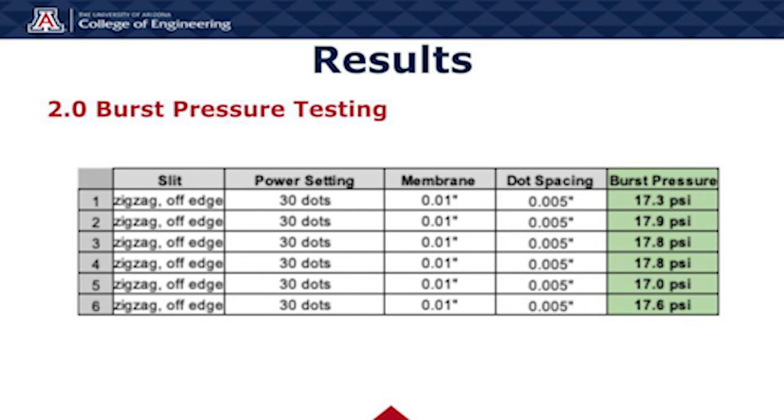The average burst pressure was 17.5 psi. While the burst pressure is not as low as the original specifications of 9.1 psi, we have shown proof of concept and our data indicates that this method of lowering the burst pressure using intentional slit geometries is possible with access to more advanced laser cutting technology. For reference, we determined that a membrane of equivalent thickness without an intentional slit geometry will burst at 24 psi. The laser cutter we used caused minute differences in the thickness of the slits resulting in weaker points throughout the cut that would cause small leaks. As a result, the pressure had to be increased past the design specifications to cause a full burst after these initial small leaks. However, while we decided with our sponsors at Ceridian that 9.1 psi would be an ideal burst pressure, the actual specifications were that the burst pressure fall between 3.2 and 15 psi, so our final burst pressure for the device is just above the upper range of the target pressure.